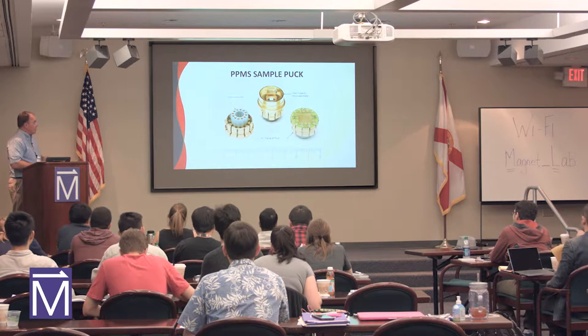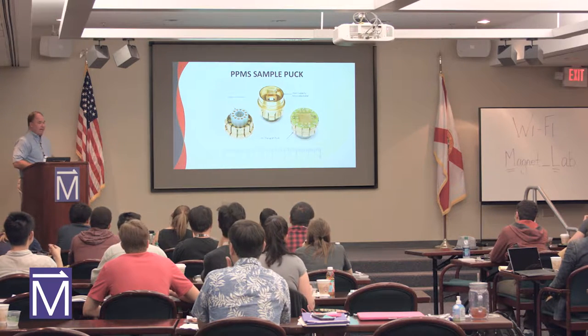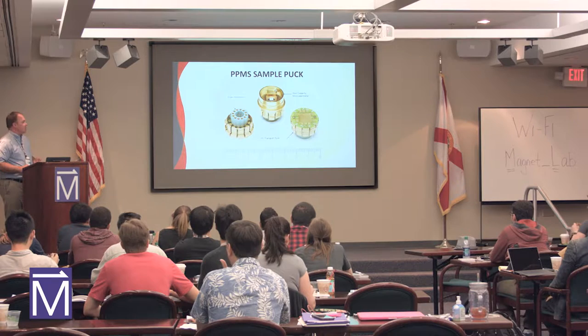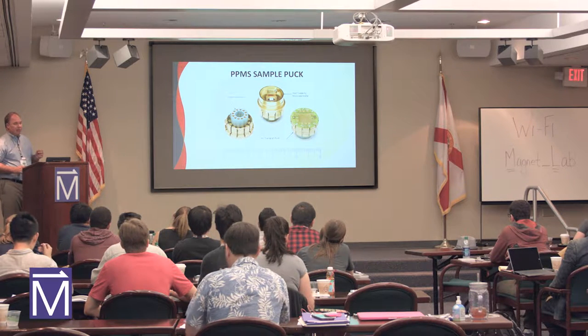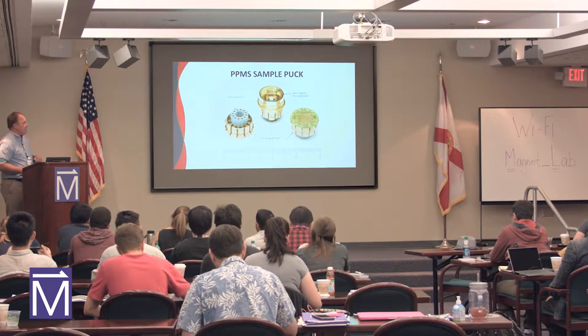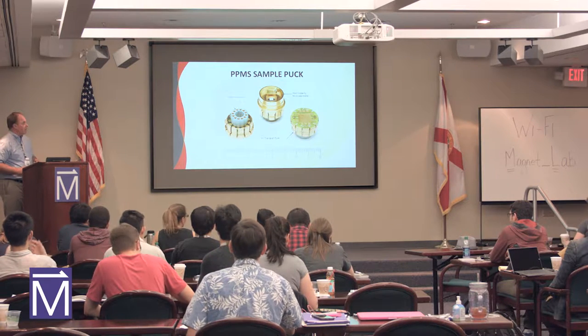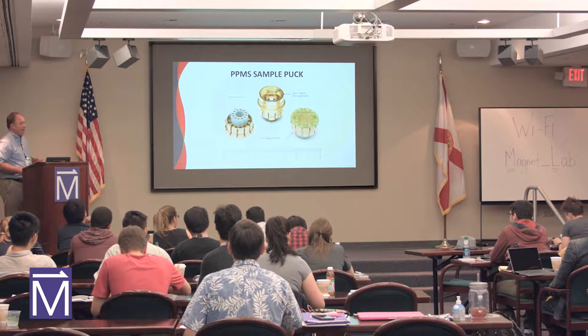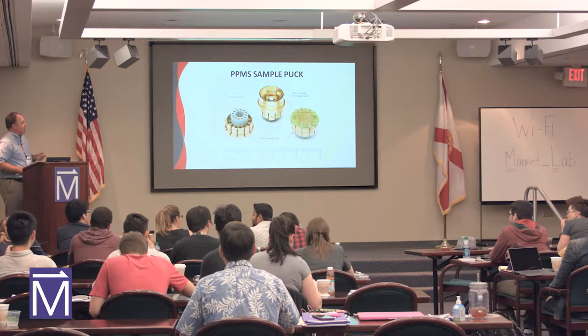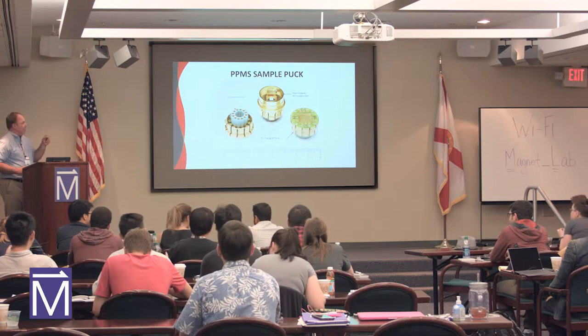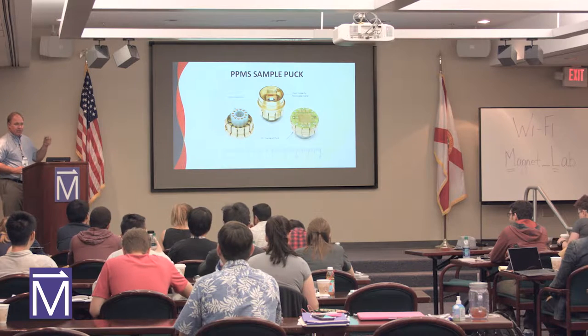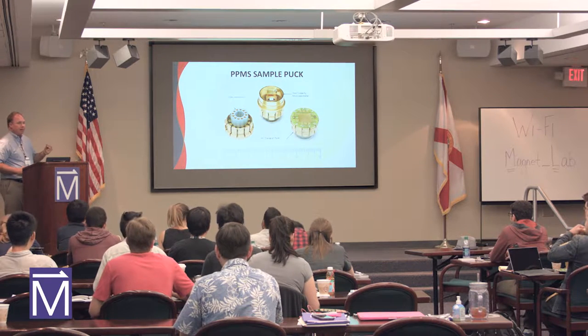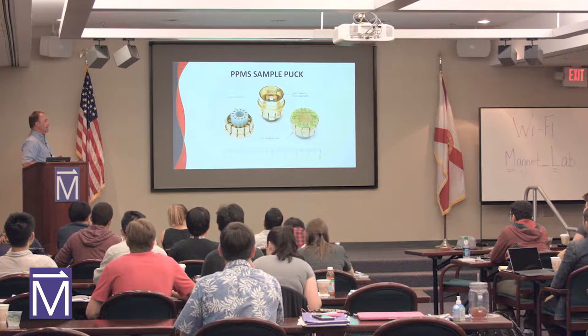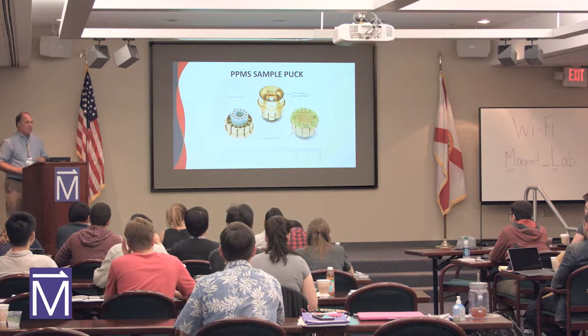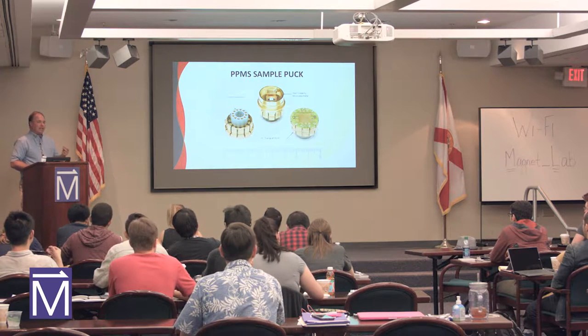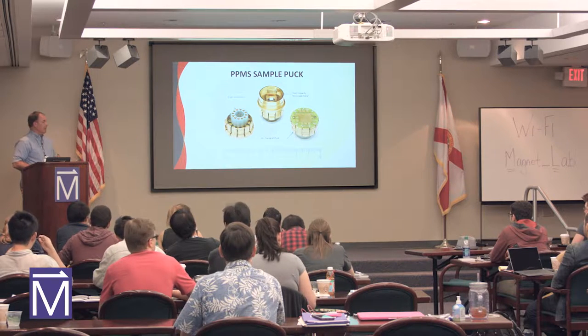So the heart of the experiments in the PPMS, the physical property system, is the experiment sample puck. So we've got some pucks on the table here that we'll pass around the room that you can share with everybody just so people can see how to mount the sample. So there's a 12-pin connector on the bottom of the puck, and that plugs into the sample chamber. There's an extraction tool that you put the puck in, slide that into the instrument, and release the extraction tool, and your sample is sitting at the center of the magnetic field in the system.